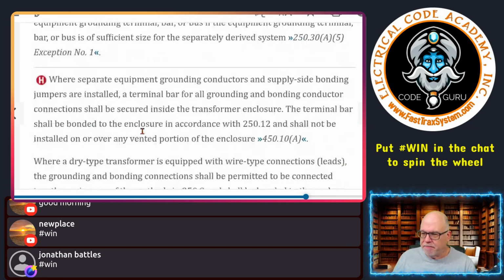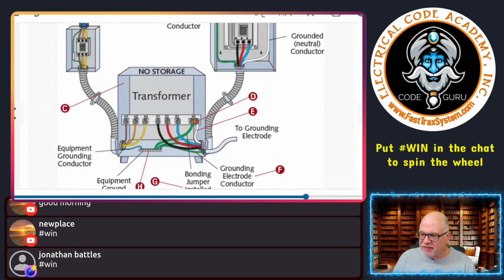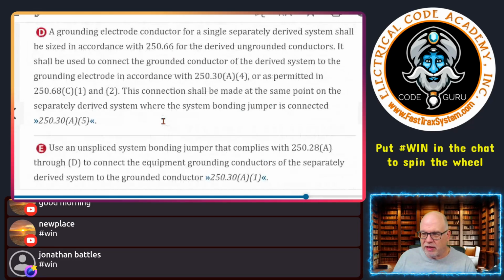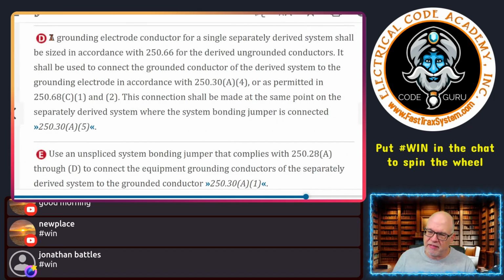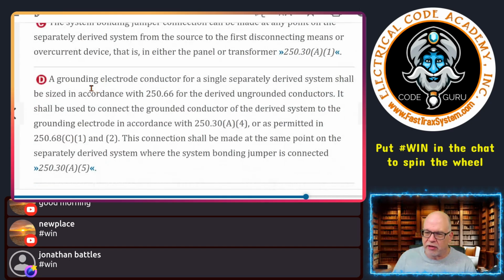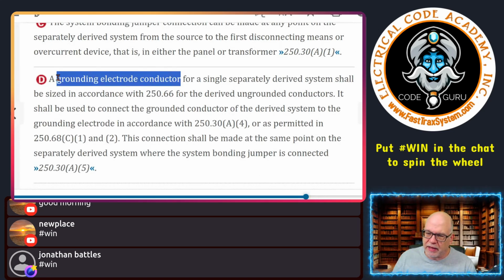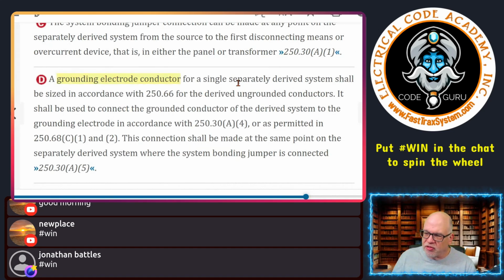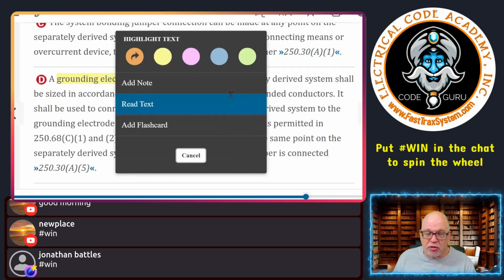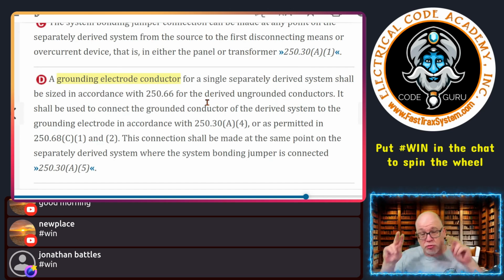D, what is D? D is talking about right here, this connection. So D obviously is talking about the system bonding jumper. It says a grounding, oh, no, it's talking about the other conductor. It says a grounding electrode conductor for a single separately derived system shall be sized in accordance with 250.66, because we are sizing grounding electrode conductors. That's what that article is for. For the derived ungrounded conductors, remember the derived conductors are those coming off the secondary. They're being derived, if you will, from the transformer.